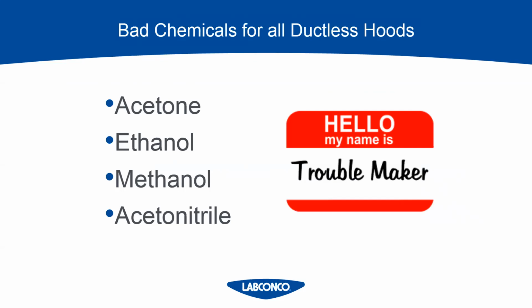The low molecular weight solvents that aren't good for carbon filtration, because they have very low filter capacities, are these four: acetone, ethanol, methanol, and acetonitrile. Anytime people come to me and say, "I have a cleaning application, we clean with acetone," I say that's probably not going to work in a ductless hood, because you're using high volumes of acetone, and that's going to fill up these filters very quickly, and it just won't make sense. If you're working with these in limited quantities, or you can close the container most of the time, it still might work. But if you come to me with an application that is heavy on any of these four, it's going to get kicked out. It won't be able to be used for any carbon filtration.